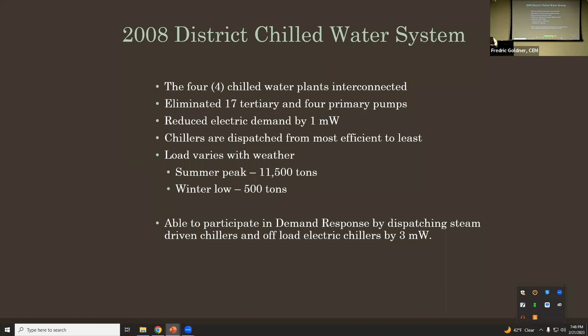But one of the things that we found, and I didn't put this on here, is that a few of the air handlers where you'd go around and test the traps and say they're cold in the summertime, they were still leaking by a degree or two, which most of us would throw off as calibration error. It wasn't. Once we turned the steam off and cut the pipes, the temperatures off the reheats became the same temperature as the outside air. So that 1 degree, 2 degrees was really 1,500 tons worth of cooling that we were doing, and 1,500 tons worth of heating that we were wasting.